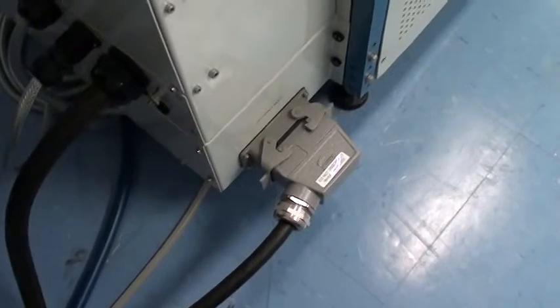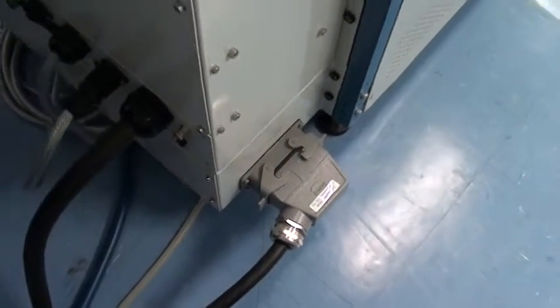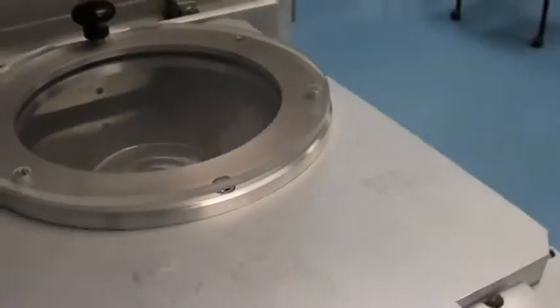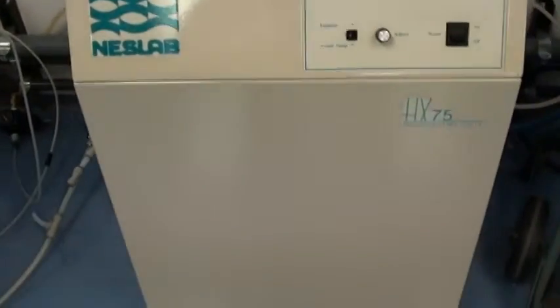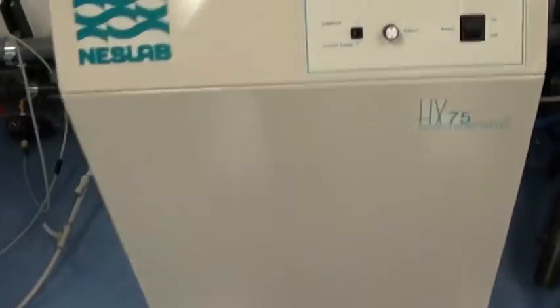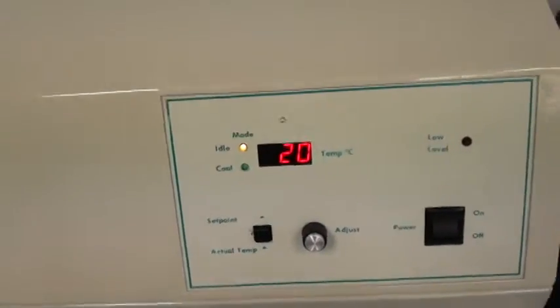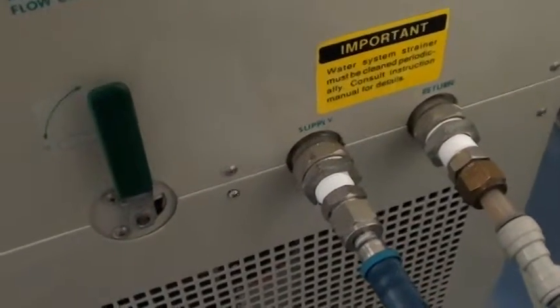Over here is the ICP generator, RF generator power — that's externally powered. This tool also comes with a Neslab HX75 air-cooled chiller. You can see its set point is at 20 and it's controlling at 20. This is the water output and return ports.